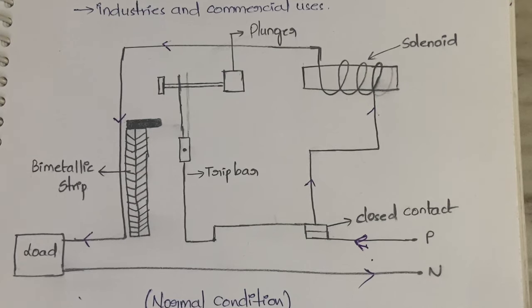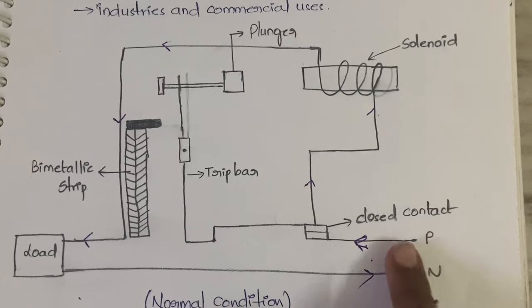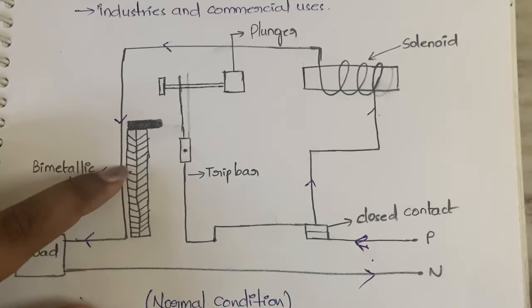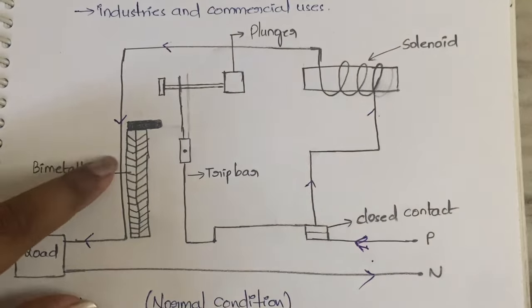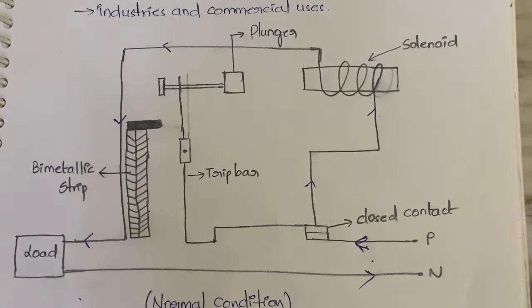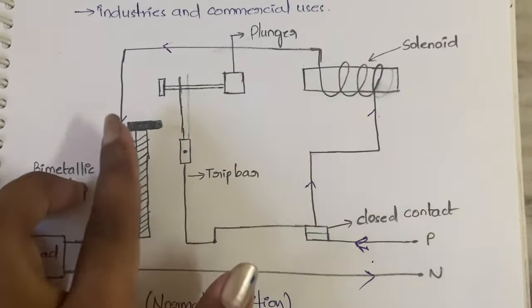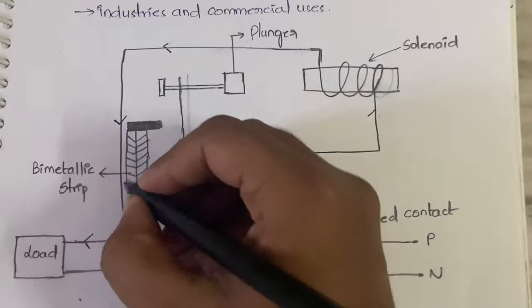When there is a slow increase in current, whenever excess current flows through the bimetallic strip, the strip will get heated up. Metals expand on heating, so the bimetallic strip will expand and bend — it will deflect. When it bends, it will hit the trip bar. The bimetallic strip bends in this way and comes to strike the trip bar.